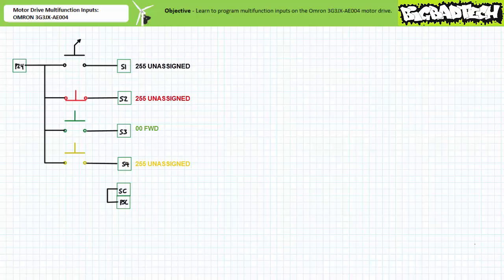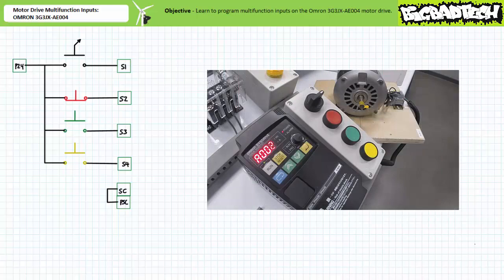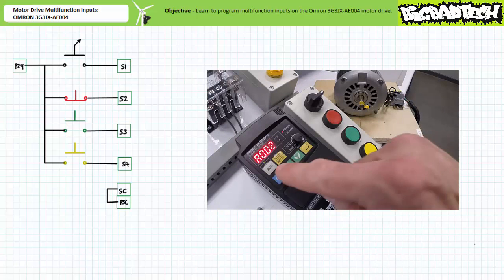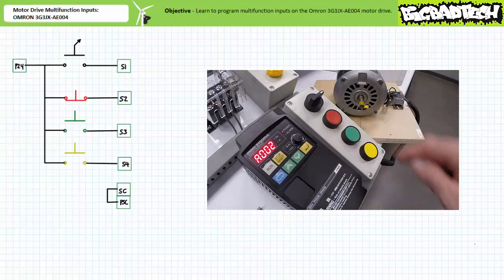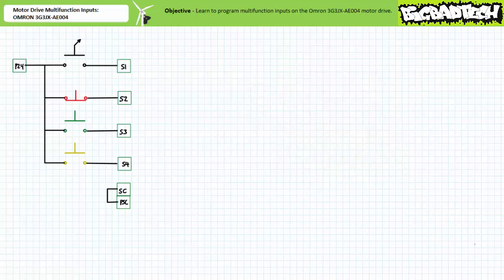This motor drive has now been programmed to recognize only input three as the initiation signal for forward operation. Now that the inputs have been properly assigned, we need to hand off control from the digital operator group to the multi-function input terminals. Navigate to extended function parameter A002, run command selection. Select mode. Decrement to 01, the multi-function input terminals, then select enter to save it. Nothing bad happens this time because the inputs have been properly assigned prior to handing off operation. This is the way to go.